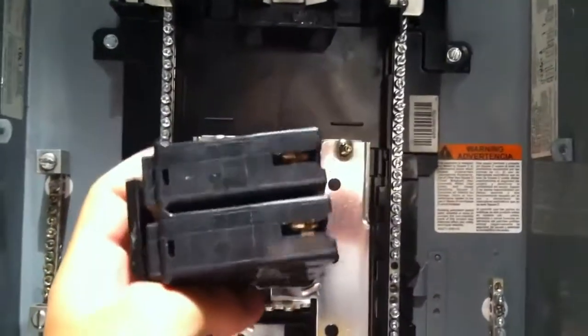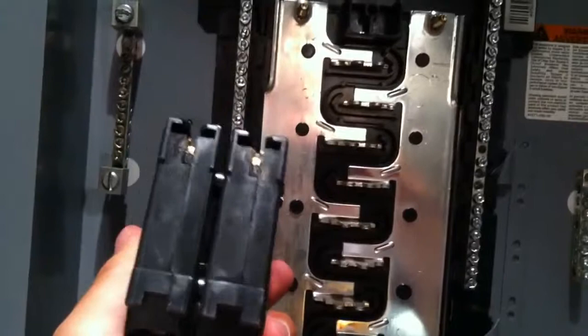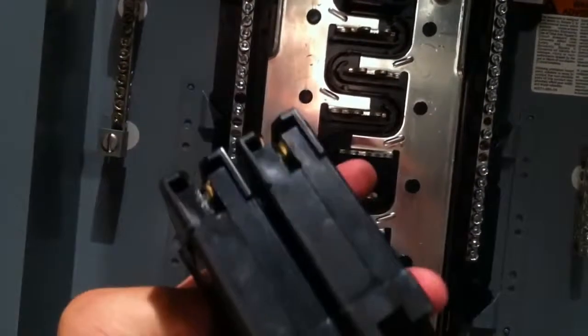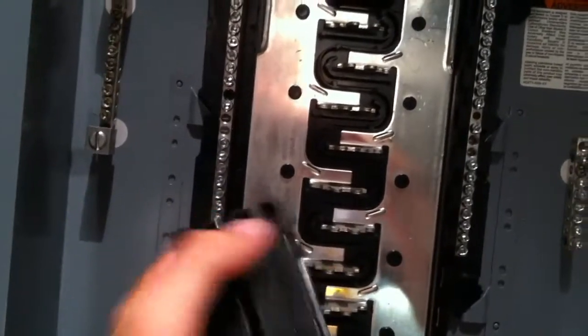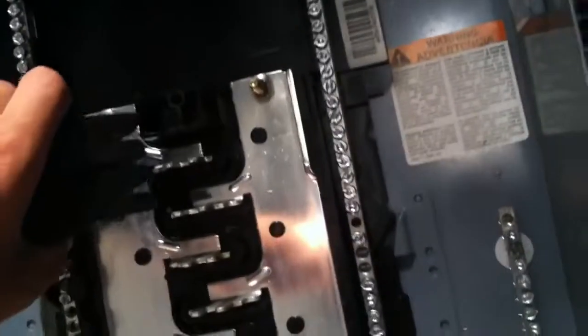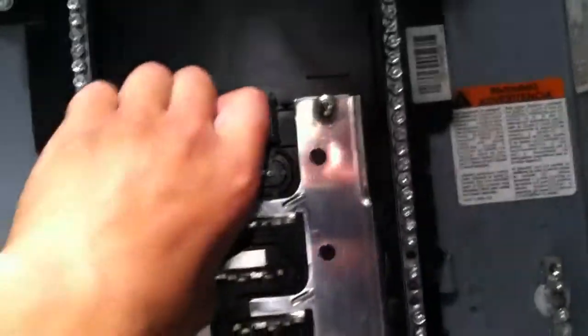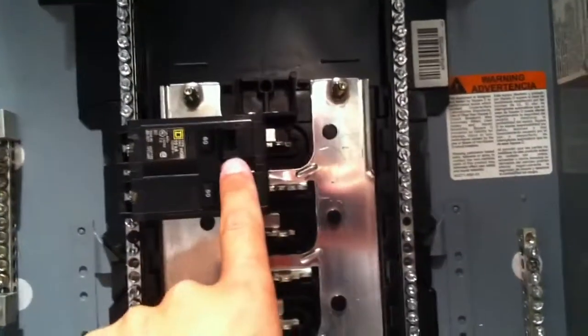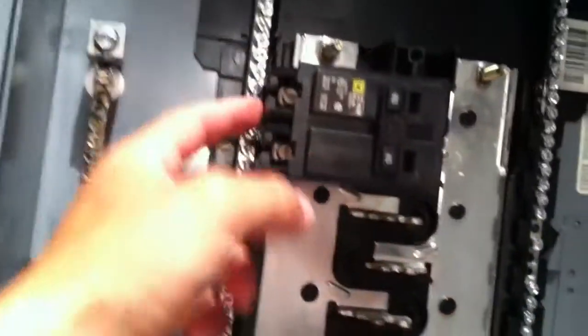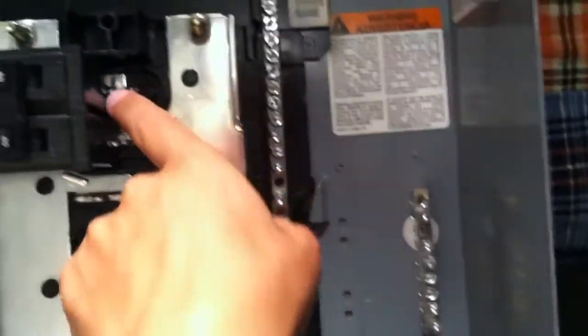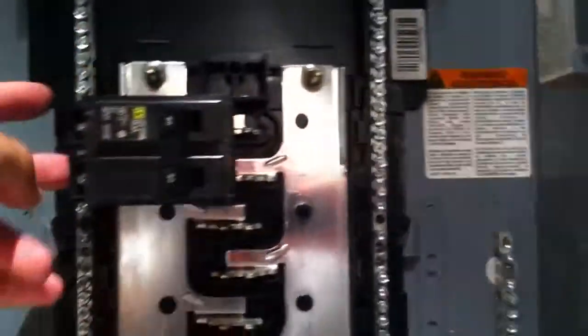Now a 240 breaker - same exact concept, except it's just two breakers tied together. This is a 60 amp breaker, which would be for something like a large air conditioner or a hot tub. So you have a prong here and a prong here, and we pop it in. These are a little more difficult to do, especially with one hand and a breaker this size, but you can see it has two breakers tied together. So you have 240 coming out, pulling from this phase and this phase - both phases. Now you have 240 coming out, 60 amps, and I'll throw the cover on so you guys can see.